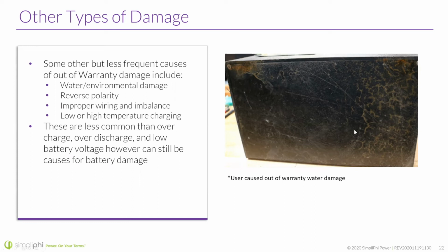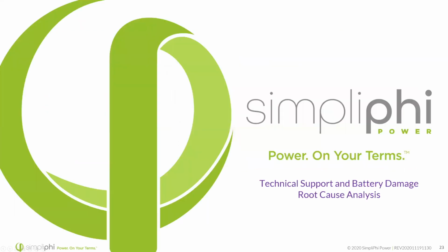This actually on the right here is an example of a water damaged battery. So you can see kind of the very clear signs externally. It's not always that way. Sometimes you might not see the signs until you open the battery, and then there's internal water damage. The batteries are not NEMA 3R rated. We offer NEMA 3R case solutions to put the batteries in, but the batteries themselves are not NEMA 3R rated. So you got to keep them in an area that's dry.